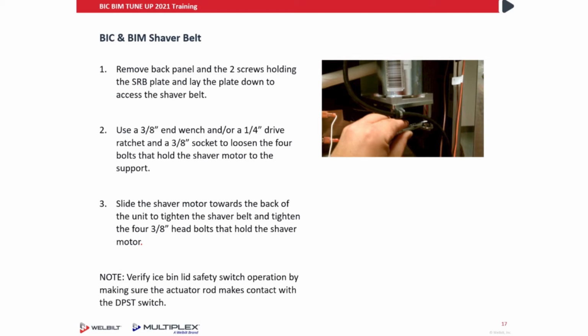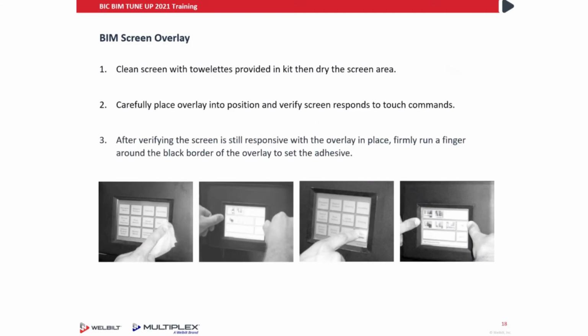Verify the ice bin lid safety switch operation by making sure the actuator rod makes contact with the DP-ST switch. On the BIM, we want to also change out the screen overlay. Clean the screen with the towelettes provided in the kit, then dry the screen area. Carefully place the overlay into position and verify screen response to touch commands. After verifying the screen is still responsive with the overlay in place, firmly run a finger around the black border of the overlay to set the adhesive.